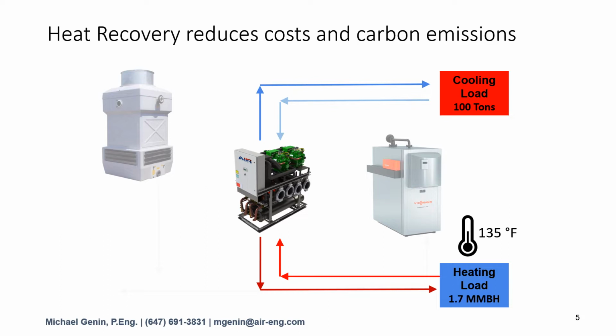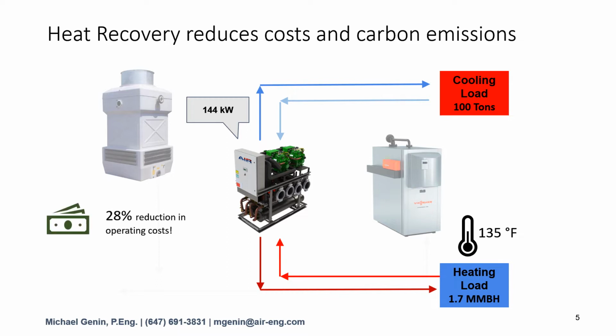Typically, while the amount of heat rejected by the chiller is plentiful, it's at a very low grade temperature. Cooling towers operate at 95 degrees Fahrenheit. The chiller needs to work harder to increase the temperature of the condenser, consuming more electricity to upgrade heat. In this case, 144 kilowatts. The cooling tower and other miscellaneous devices are turned off, and the boiler is also turned off. However, this results in a 28% reduction in operating costs and a 95% reduction in carbon emissions. Note this is using Ontario utility rates.